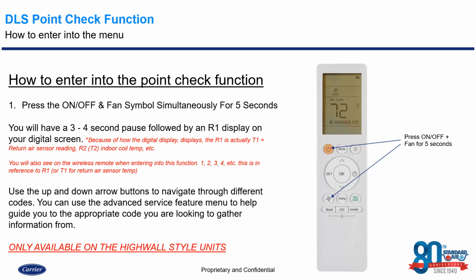Okay. So it's important to note on here that we have a different functionality on how we get into this versus the older style. So we're pressing the on and off and the fan button simultaneously together for 5 seconds to get into this point check function. So why do we care about getting into this point check function? Well, this is a great way on the high wall units only. So units that have a digital display where we can see what the actual unit is reading for return air temperature and coil temperature, depending on if we're troubleshooting or if we're looking to get a ballpark idea of the delta T or return air versus supply air for these units in order to check charge, or if we're just doing routine maintenance, all while not having to take the unit apart and only having the knowledge right now that we have, plus our wireless controllers to access it.